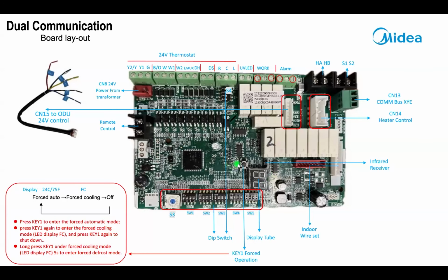Right here is the forced operation button. If you press it the first time, it puts the unit in forced auto mode. It uses a 24 C set point and runs auto mode off of that set point. What's 24 in Fahrenheit? 75. Thank you. Couldn't remember. Well, I've done this once or twice. All right, push it again, and it puts it in forced cooling with a 24 C set point or 75 F.